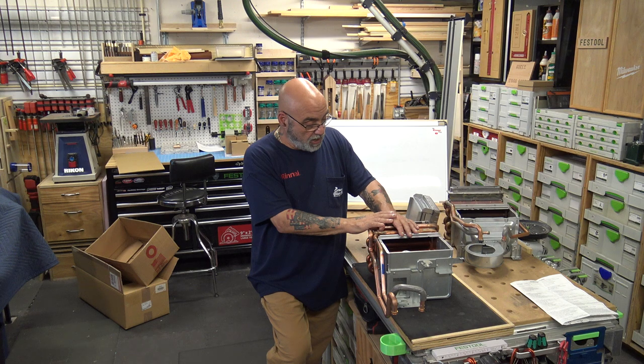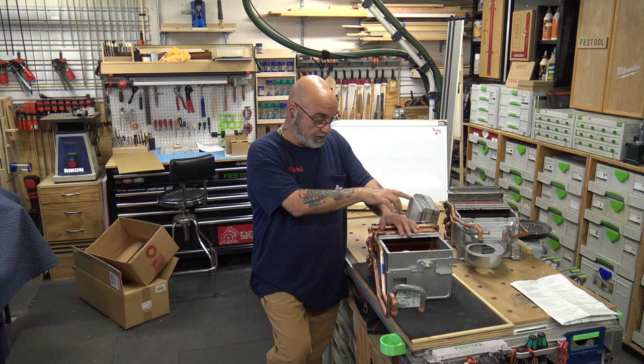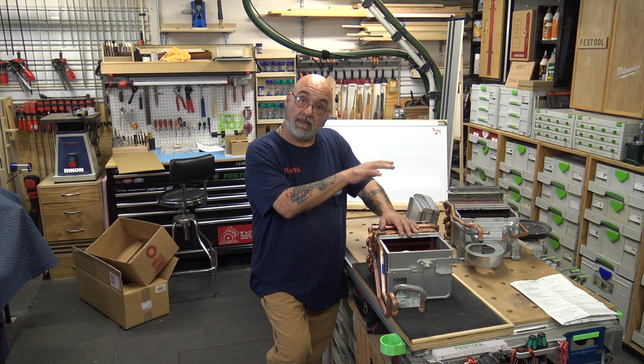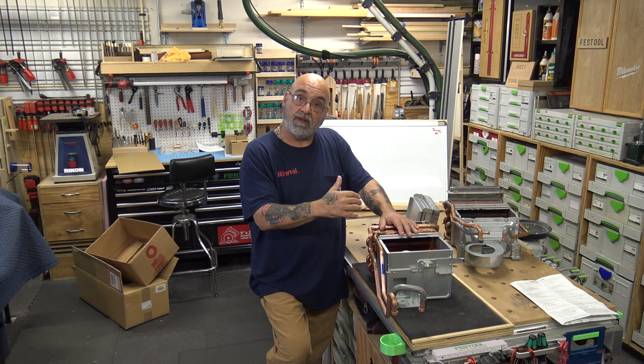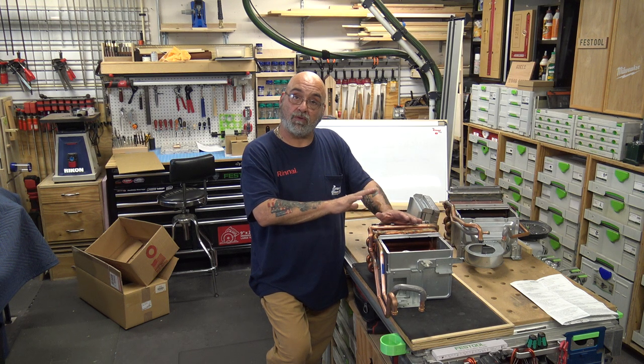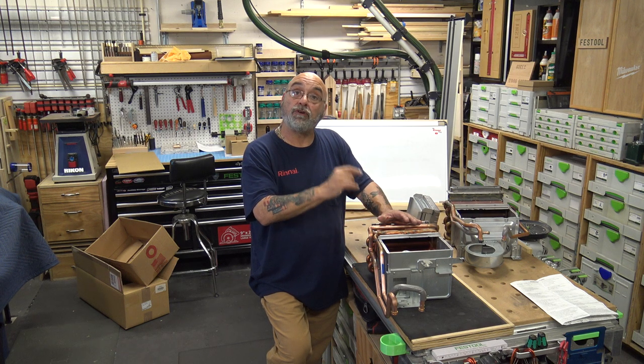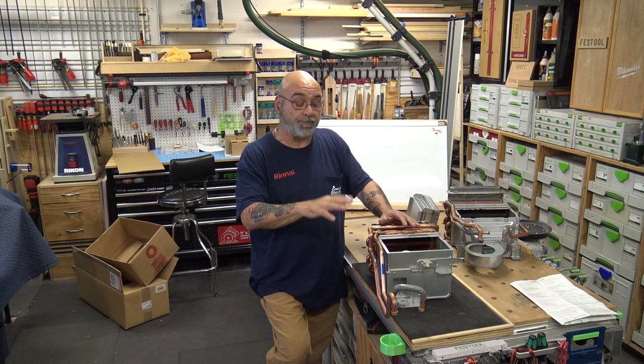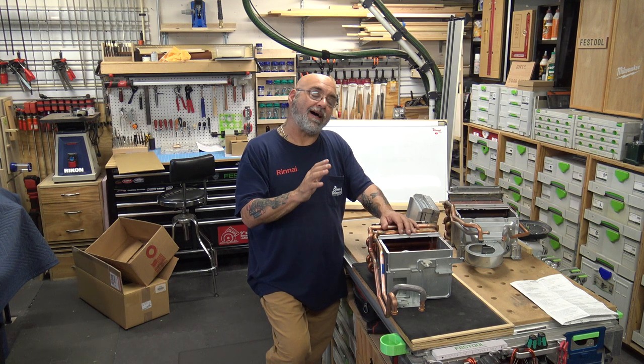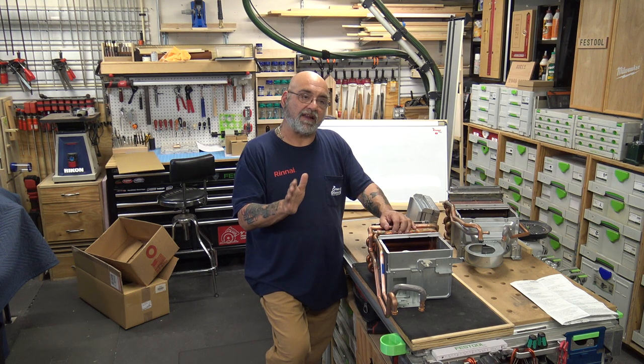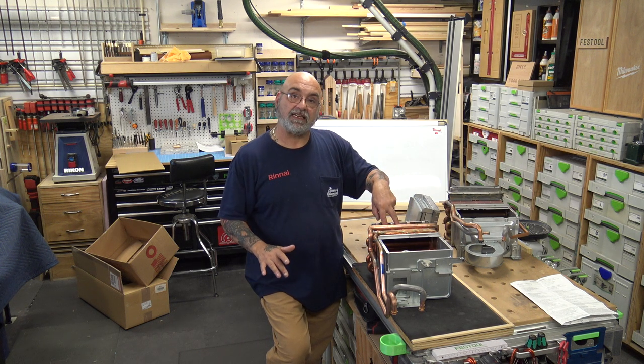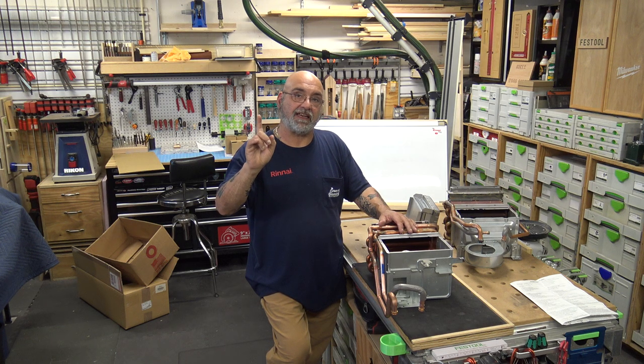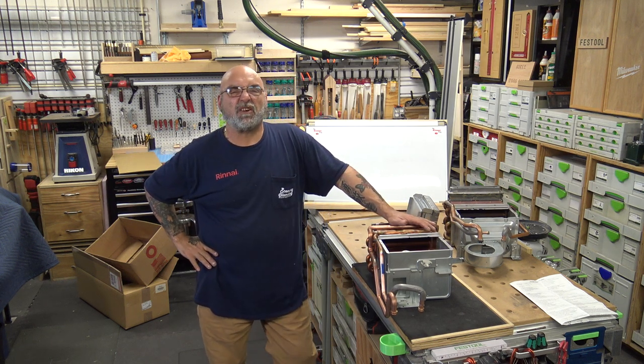Okay, so that is your code 10. Follow the seven steps in the pamphlet in the front cover, and have your parts, your tools, your gasket set all ready so that you can rebuild this. Your denatured alcohol to clean off the gasket glue, put everything back together. Now, I can tell you that in a lot of instances, the only gasket that we really replace is the one that houses the two flame sensors and the igniter, because that thing is pretty deteriorated.